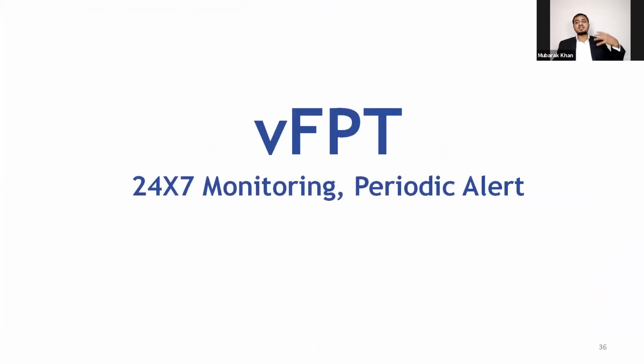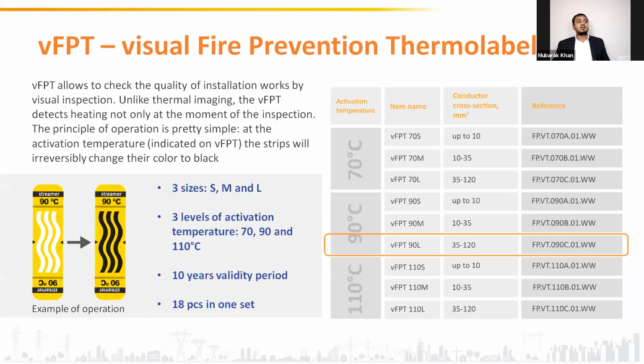Okay. Now coming to the second method of monitoring, which is VFPT, 24/7 monitoring and periodic alert. The VFPTs allow you to check the quality of installation work by visual inspection. Normally what we need to do is wrap these stickers around the electrical joints. These are the only stickers worldwide which can be used on an electrical joint, wrapped properly in a 360-degree manner. So it can be wrapped around the electrical joint, and whenever the temperature of the joint reaches the set point of the sticker, the color of the sticker will change from white to black. Initially there will be white stripes on yellow, then it will convert to black stripes on yellow.